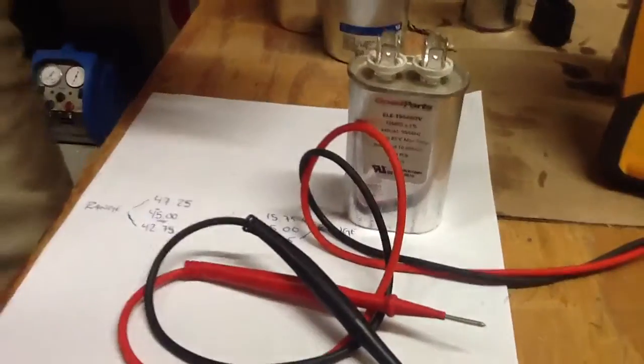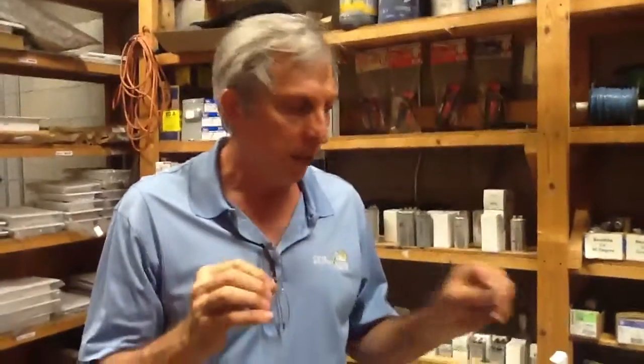So that's all there is to it. Just remember, when you put your meter on microfarads, look at your capacitor rating, plus or minus your 5%, 6%, some are 10%. Do the math, and that's all there is to it. If you have any questions, just give us a call at Jones Air Conditioning, 239-596-5855, or go to jonesairconditioning.com. Please share, please subscribe, and please comment. Thank you.